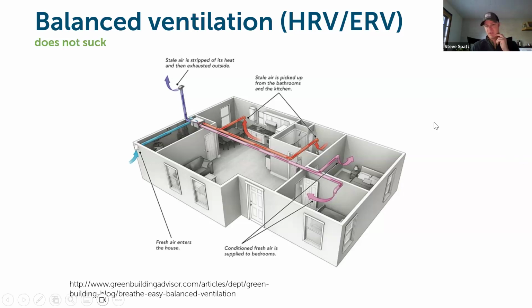So you can be filtering out dusts and pollens and other pollutants into the building as well. And in balance, meaning that the exhaust side of the system and the fresh air side of the system are to be balanced within about 10 to 15% of each other for flows. So you're not creating negative pressure differentials in the house through exhaust only systems or through suction. You're keeping a neutral pressure plane within the building with a good effective ventilation system installed.